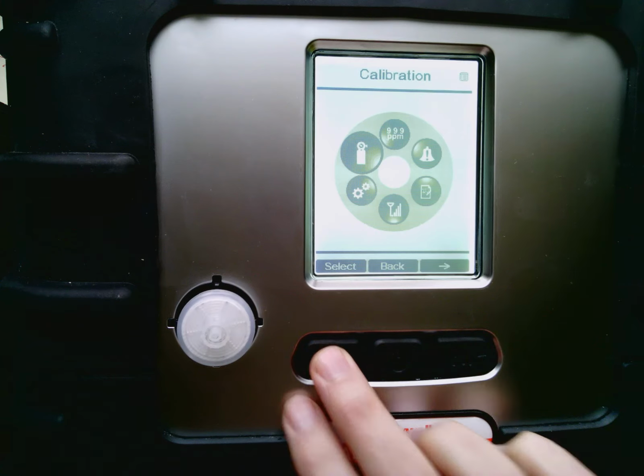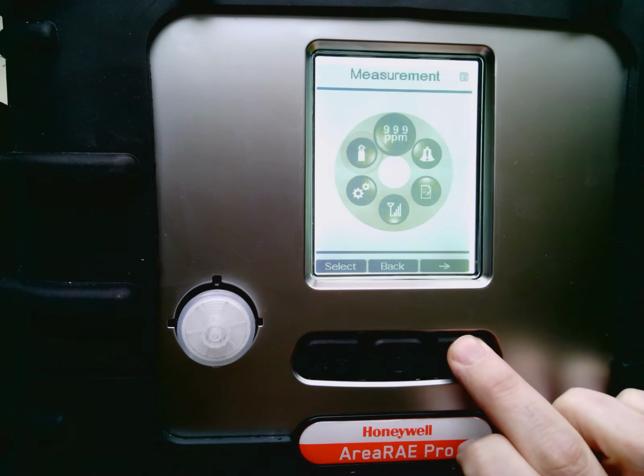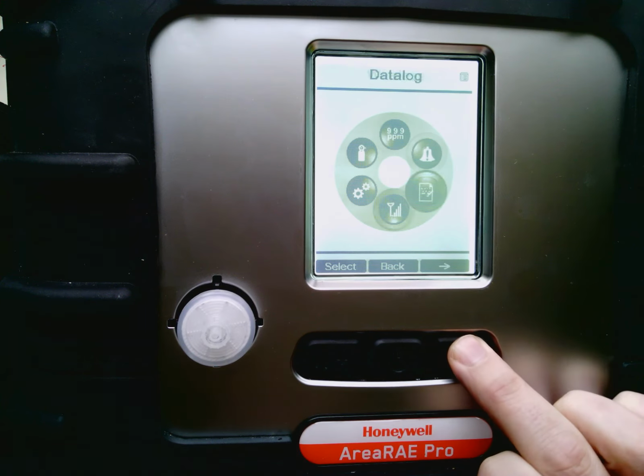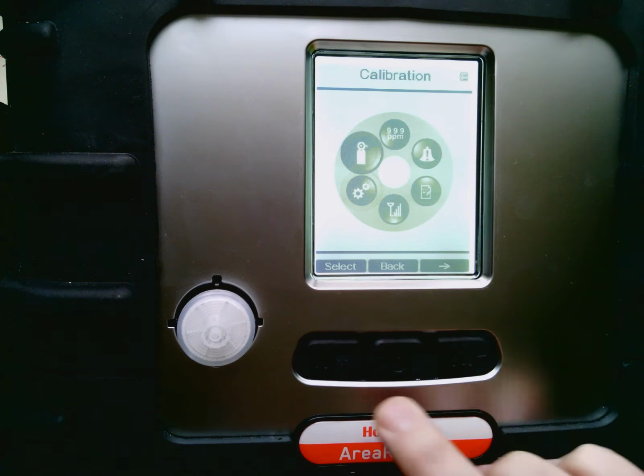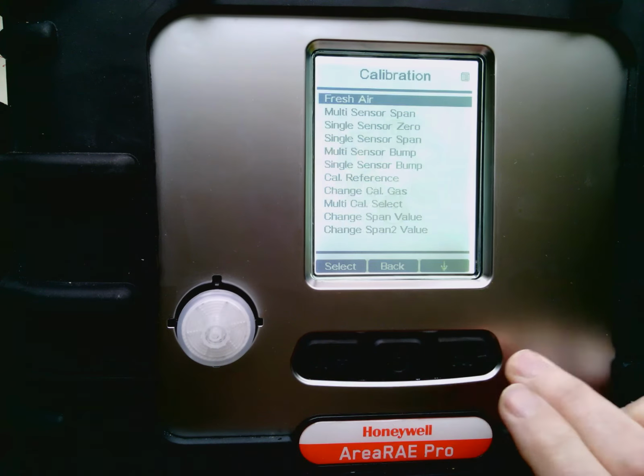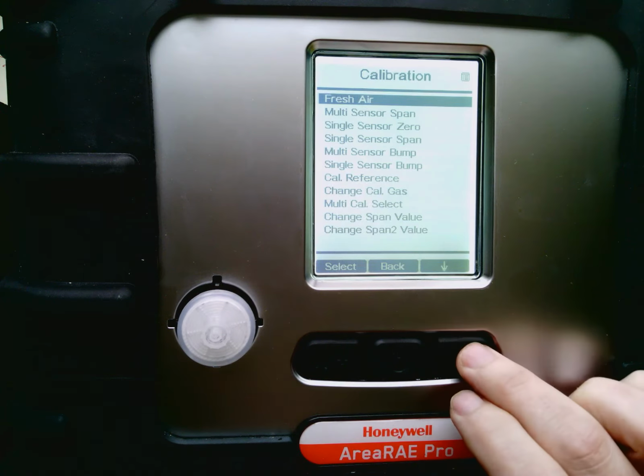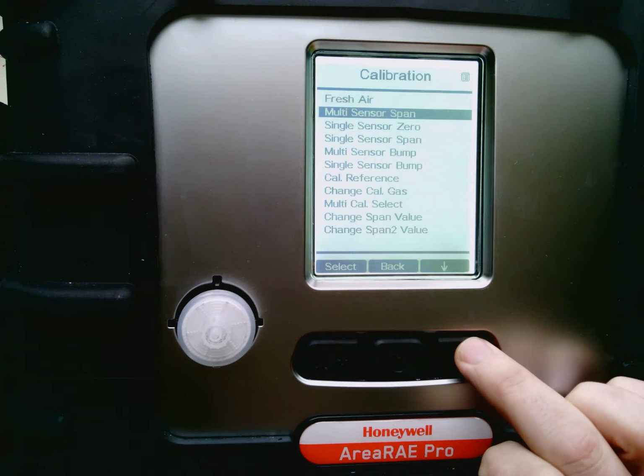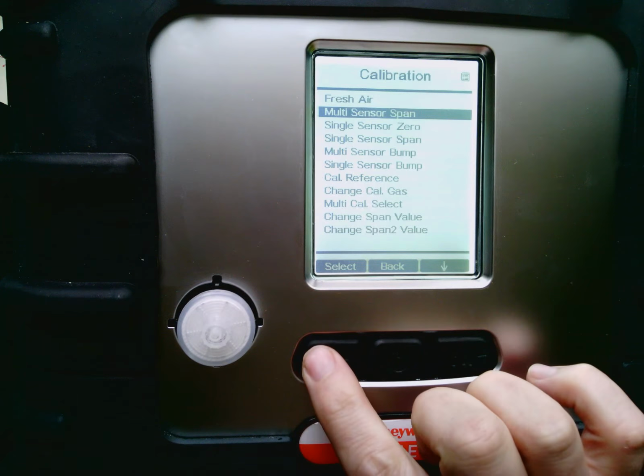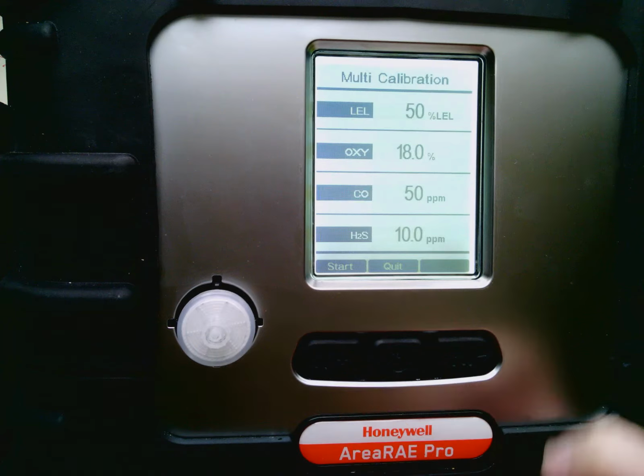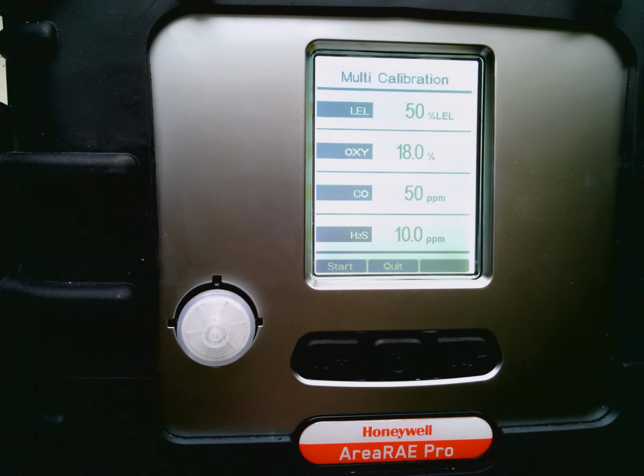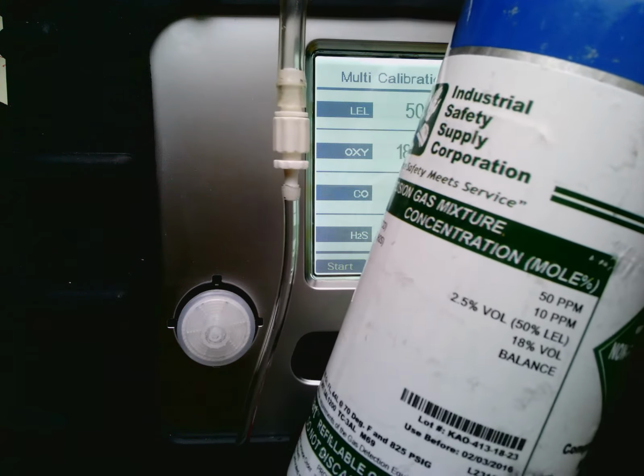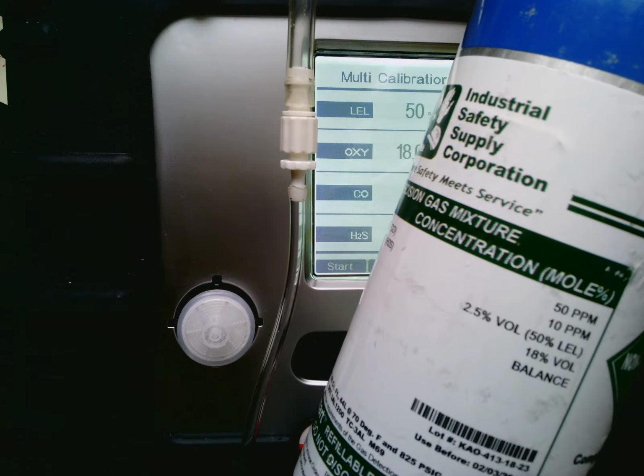You'll notice that, using the soft key, I'm just going to mode around so you can see it change. We're going to go back to calibration and hit the select button. Since we already performed a fresh air calibration, I'm just going to mode down to multi-sensor span and hit select. It's going to give us the concentrations that the sensors are looking for. And obviously what's important is that you utilize a bottle that has those particular concentrations in it.